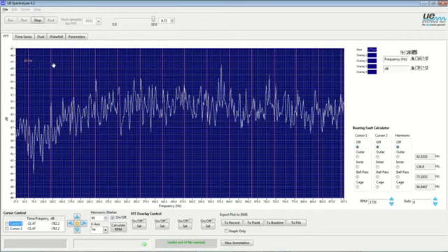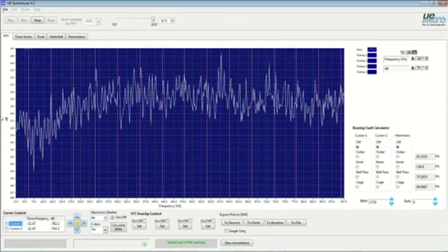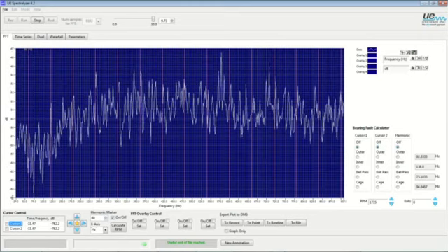Again, I'm going to adjust this so we can fill the screen up and be able to see more of the data. That'll work right there. And what we can see on here is a different frequency spectrum. Again, with the 60 hertz cursor on, over here at 60 hertz, there is not a frequency spike or peak, but there is one here at 120 hertz, a small one at 180, another at 240, and that is shifted just slightly out here at 360 and nothing else out here.